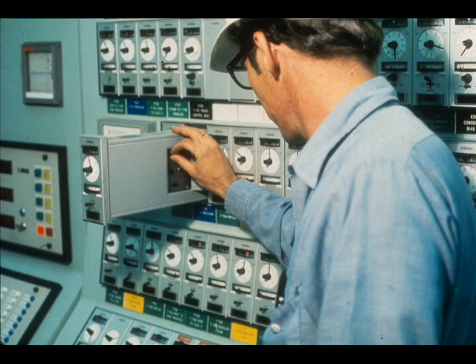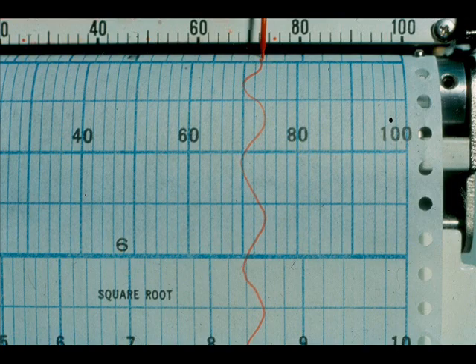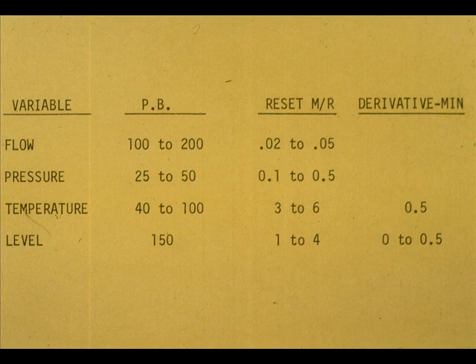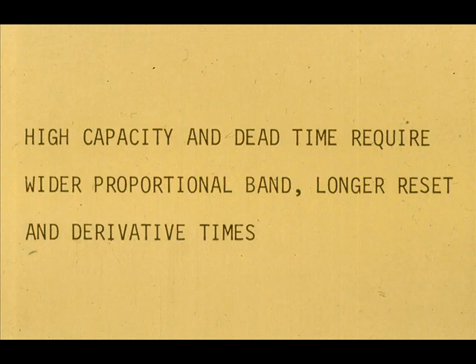Now for a few practical suggestions in regard to tuning. If the process cycles while on manual control, don't try to tune it — the external disturbance must be eliminated. A majority of control loops pose no special problem for tuning. Ballpark settings for different variables are shown here, and final adjustments can be made as time allows; a similar guide is in the workbook materials. A judgment has to be made concerning the system capacity for level, temperature, and some pressures. High capacity and dead time require wider proportional band, longer reset, and derivative times.